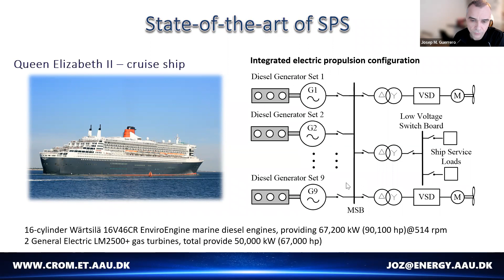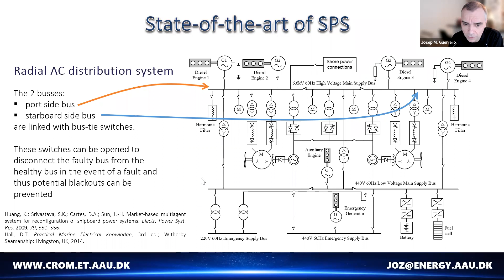Right now, a major part of ships have at least 2 separate buses, connected to a pair number of diesel generators. Then, with transformers—for instance, a delta-Y transformer to eliminate the 5th and 7th harmonics—you can step down to low voltage. You can also see harmonic filters here, which we'll talk about later, especially when moving on to AC.